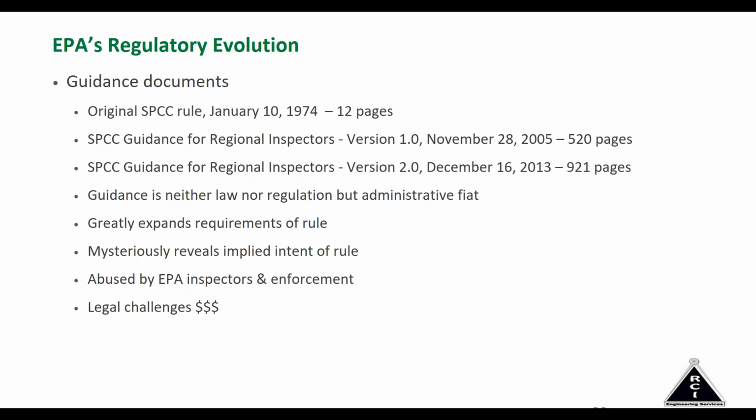I'll give you an example of one way that they've expanded the rule, and this has to do a lot with any facility, really, but a lot of our bulk fuel, a lot of our petroleum marketers who have bulk fuel plants. The guidance document says that filling a tank off of a transport is no longer a one-person operation, unless you have high-level alarms and shut-offs and automations that will shut the system down and keep it from overflowing.